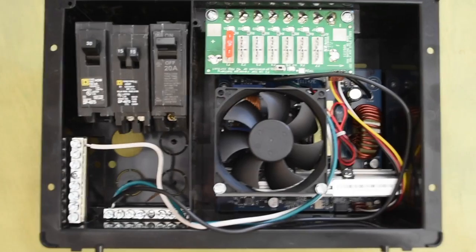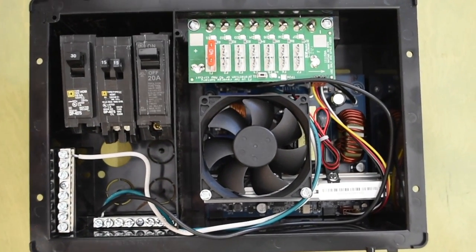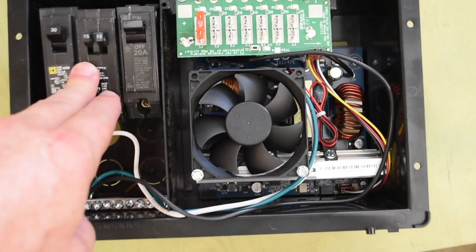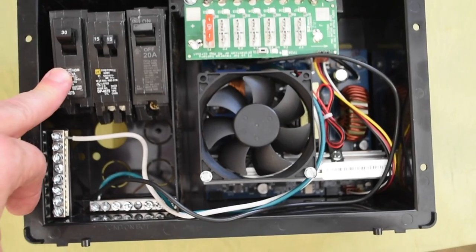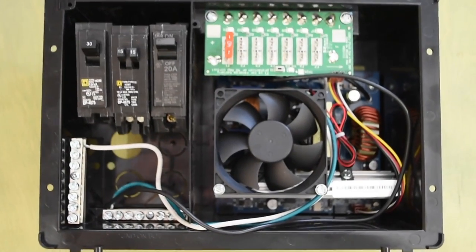I also want to point out that for this configuration, I've oversubscribed the main breaker with two 15 amp and a 20 amp totaling 50 amps. The theory is that these appliances won't be running simultaneously at any given time, nor at maximum power.